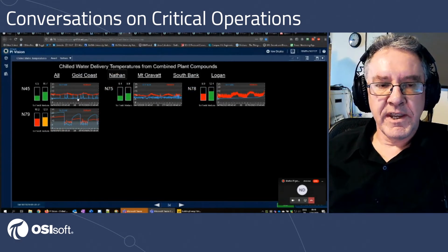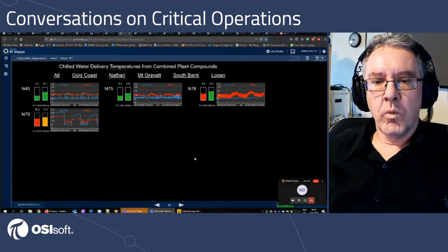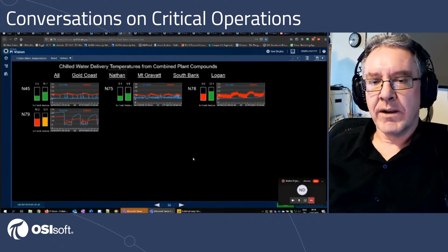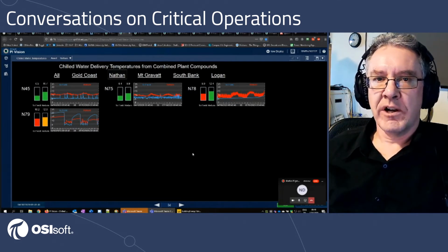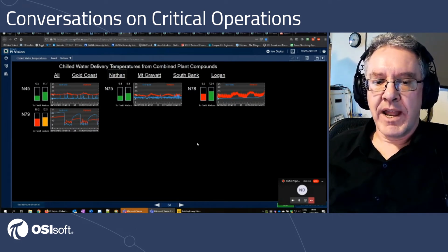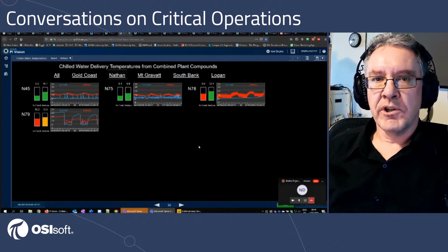The new chiller house is going to have 2 small chillers and 2 large chillers initially, because we're in Brisbane, we only have high load for about a quarter of the year over summer. The rest of the year we see very flat demand, and if we only had one low load chiller and it went down, we would have to short cycle one of the big chillers. So out to our consultants we went: no, we want 2 small chillers, 2 large chillers.